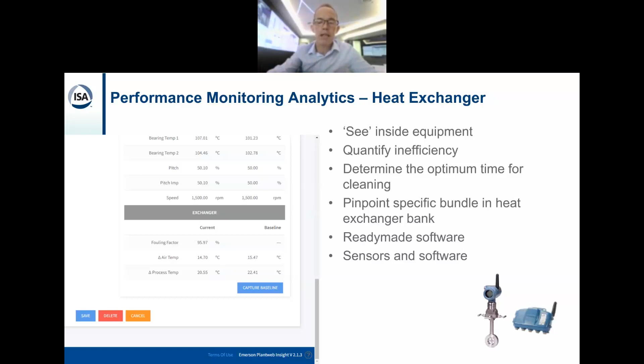Now, the analysis needs real-time data. The most reliable way for software to determine efficiency of equipment is to fully instrument the equipment. The inlets and the outlets, with temperature sensors, as well as flow meters and pressure sensors, depending on the type of equipment. Now, running wires in existing plants for lots of new sensors is not practical. Using wireless HART sensors is really the most practical way. Note that the required 4-in-1 temperature transmitters that you see here and industrial DP flow transmitters may not be available for other wireless technologies. Okay, and on a separate note, you don't have to develop, test, and pilot software. These apps are ready-made and support HART IP as well as OPC UA. So you can install and use them, just like that.